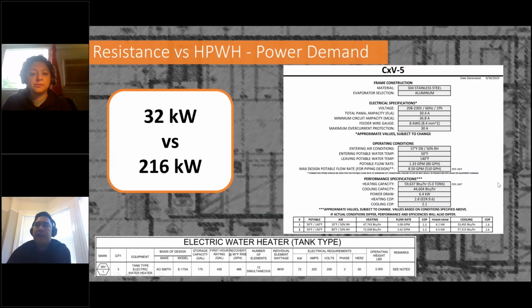So now we're comparing. We'll definitely try and go all electric, but we want to compare resistance with heat pump water heaters. Right now, the top right is the CXV5 heat pumps, and the bottom left is the resistance water heater spec. You can see the power draw on these two units, 6.4 kilowatts versus 70 kilowatts. We have 5 heat pumps, so 32 kilowatts total.